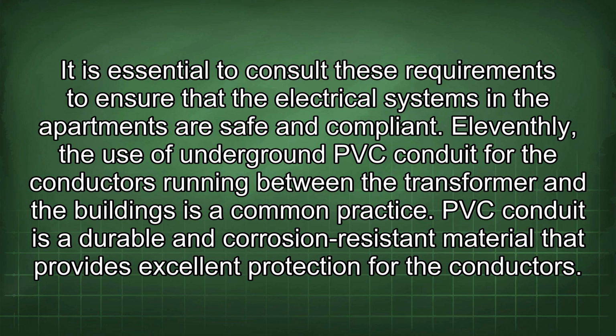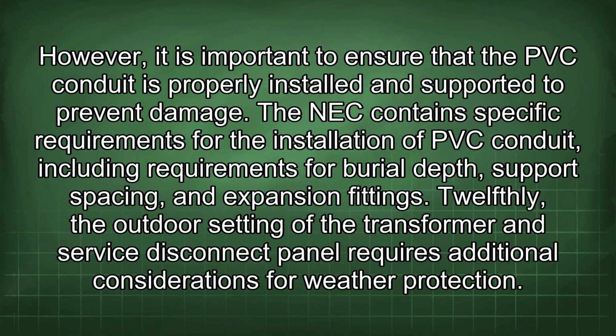PVC conduit is a durable and corrosion-resistant material that provides excellent protection for the conductors. However, it is important to ensure that the PVC conduit is properly installed and supported to prevent damage. The NEC contains specific requirements for the installation of PVC conduit, including requirements for burial depth, support spacing, and expansion fittings. 12thly, the outdoor setting of the transformer and service disconnect panel requires additional considerations for weather protection.